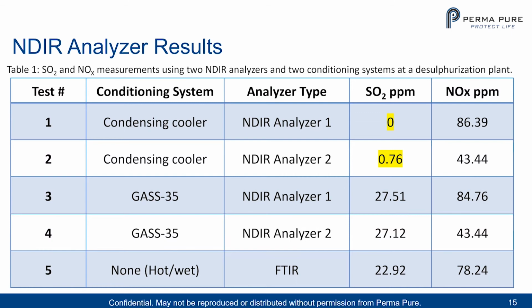You've got to have the equipment show that it's working and it's calibrated properly. Let's look at those same conditions again with the GASS-35, with test 3, with NDIR analyzer number 1. That's the same sample as in test number 1. There we have an SO2 of 27.51 parts per million and NOx is 84.76. Test 4 shows a similar SO2 level of 27 versus the NOx at 43.44.